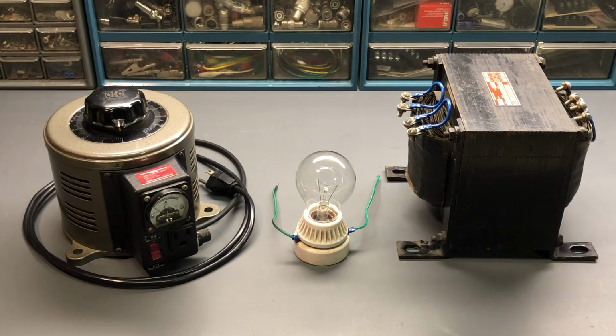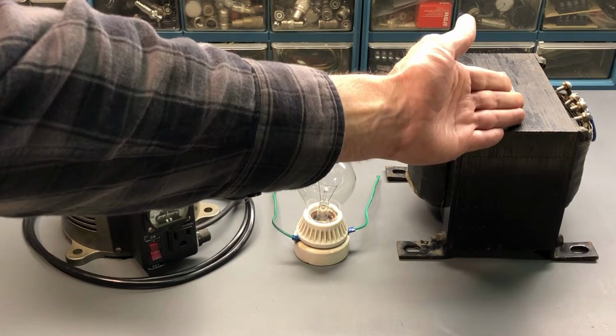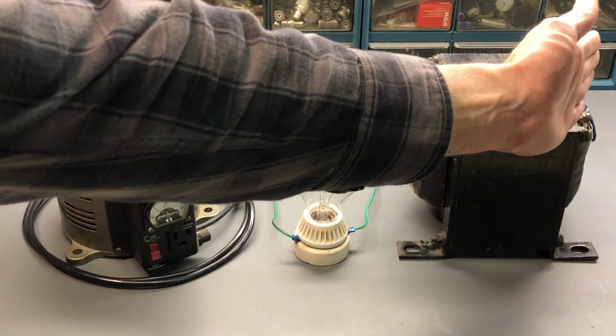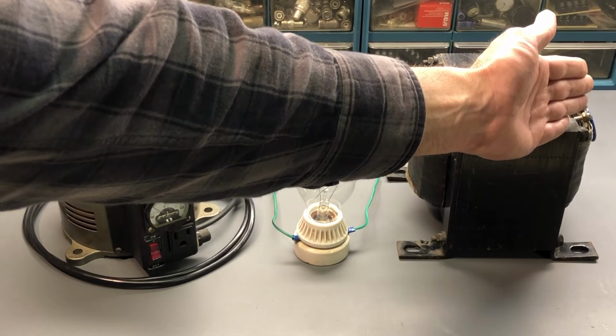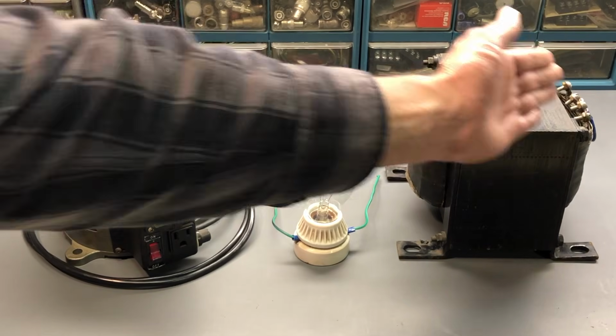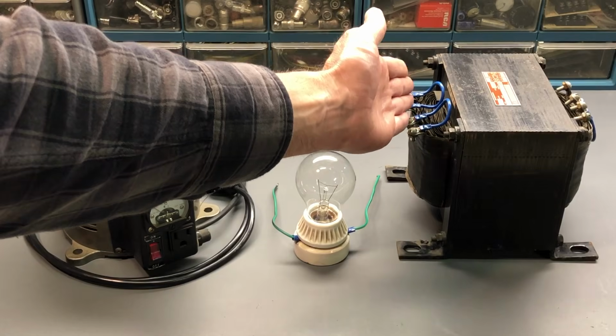So they have non-polarized plugs in most cases, and if that plug is turned one way versus the other way, it's a 50-50 chance that you have the hot AC line connected to the chassis. So you'll get a nasty, if not lethal, shock if you were to come in contact with that chassis when testing the equipment. So an isolation transformer provides electrical isolation from the AC line in the shop or the facility that you're at, and the secondary side, which is powering the device that you're testing.